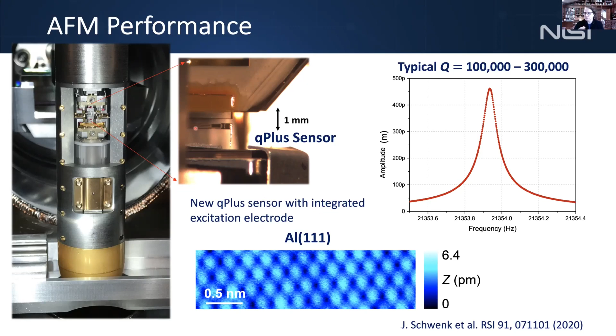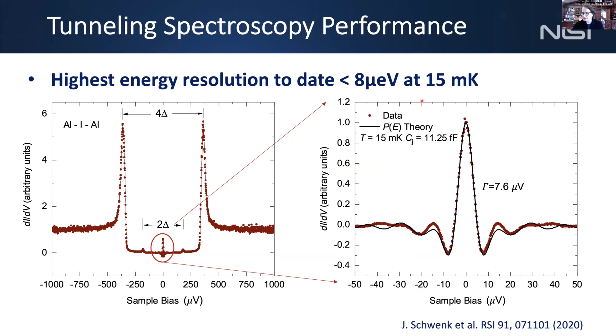The STM performance also got improved. This is a superconducting Josephson measurement with the aluminum tip and aluminum sample. If you look at the center peak here, the Josephson peak, now this is on a microvolt scale, 50 microvolts. You can see we can resolve that to better than 10 microvolts. So now we have kind of the perfect instrument that can do high resolution STS, both near the base temperature of 10 to 15 millikelvin, and AFM measurements.